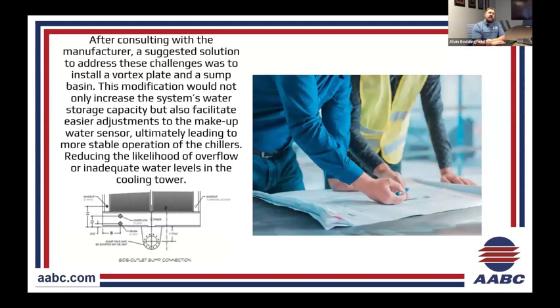So going back into the tower, we decided to reach back out to the tower manufacturer and said, okay, what can we do? We have the third option of adding the sump and the vortex plate. Obviously, we can't just add the sump, so we've got to add both. So consulting with the manufacturer, the easiest solution was, hey, let's add the capacity. Let's just add the sump at the bottom of the tower. It'll add a little bit of capacity to it. That way, once the water goes down, it was another way of doing it.